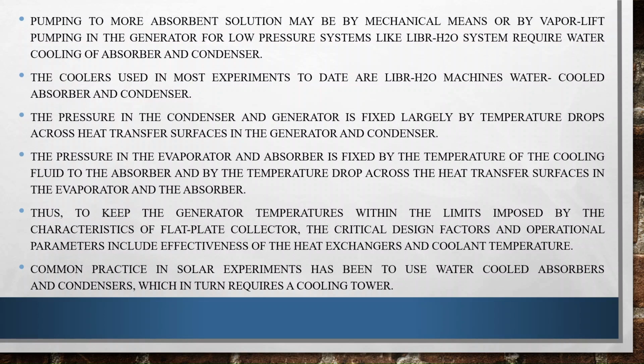Pumping to more absorbent solution may be by mechanical means or by vapor lift pumping in the generator for low pressure systems like the lithium bromide H2O system that require water cooling of the absorber and condenser. But in the case that we saw in our block diagram, we are using pumps, and the coolers used in most experiments to date are lithium bromide water machines with water cooled absorbers and condensers. The pressure in the condenser and generator is fixed largely by the temperature drops across the heat transfer surfaces in the generator. The pressure in the evaporator and absorber is fixed by the temperature of the cooling fluid to the absorber and by temperature drops across the heat transfer surfaces in the evaporator and the absorber.